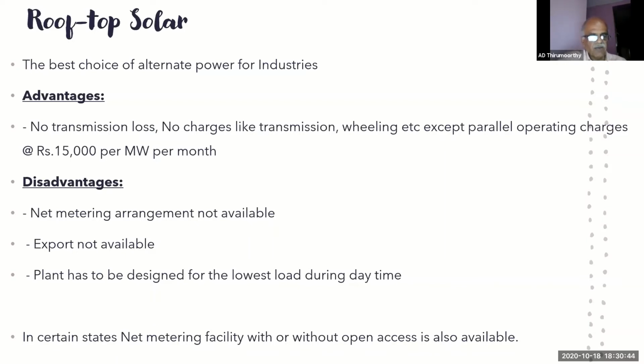Net metering is not available here in Tamil Nadu, particularly in Tamil Nadu. Net metering is not available for HT industries. So export is not available. You cannot export. You have to provide a reverse power flow relay in case generation becomes excess than the load. You have to curtail your generation. So that is the type of arrangement you should have when you go for rooftop in HT industries.